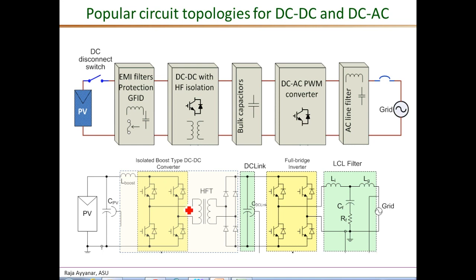The DC link itself is made of an array of electrolytic capacitors, although newer designs and current research are focusing on reducing the capacitance requirement so that it can be supported by film capacitors, which are much more reliable than electrolytic capacitors. The DC-to-AC PWM stage is very often implemented using a full bridge or H-bridge inverter as shown here, with either an L or an LCL filter.